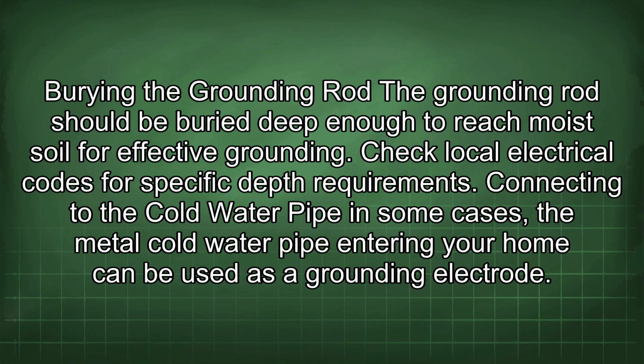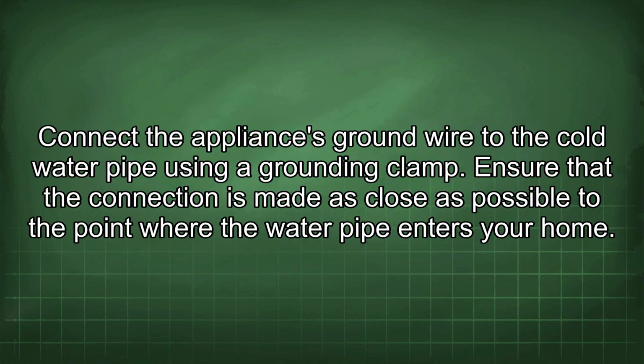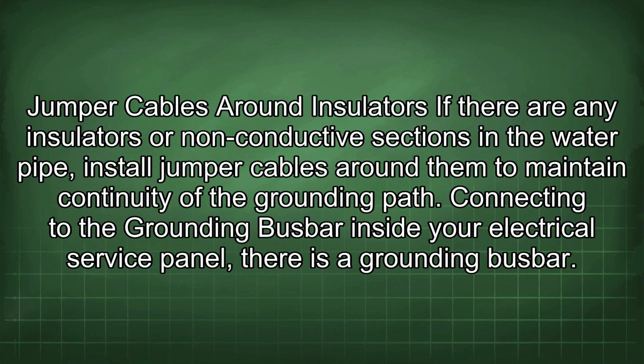Connecting to the cold water pipe. In some cases, the metal cold water pipe entering your home can be used as a grounding electrode. Connect the appliance's ground wire to the cold water pipe using a grounding clamp. Ensure that the connection is made as close as possible to the point where the water pipe enters your home. Jumper cables around insulators. If there are any insulators or non-conductive sections in the water pipe, install jumper cables around them to maintain continuity of the grounding path.